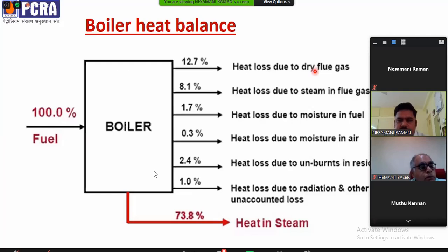If you see the formulas for calculating all these losses, heat loss due to dry flue gas, heat loss due to steam in flue gas, due to moisture in fuel and due to moisture in air, these four losses, which account for almost 12 plus 8 plus 1.7 plus 0.3, about 22% of the loss, will be proportional to the stack temperature. Meaning if you increase the stack temperature, this 22% will keep on increasing. If you reduce the stack temperature, we can recover some amount of energy from these losses, thereby the total efficiency of the boiler will increase.